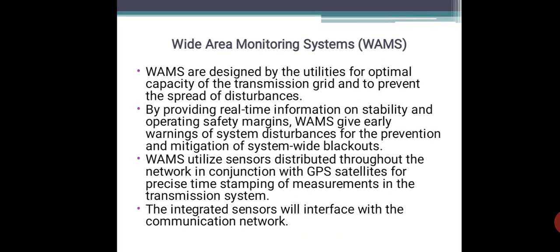Now let us discuss one of the most important devices in the transmission system, that is the PMU. The long form of PMU is phasor measurement unit. It is also called a synchrophasor. What this device does is take a snapshot of the power system. Let me brief once again. Whatever the bus voltage is, the phasor of that bus voltage and the phasor of the branch current, plus some additional information like the location and other network parameters, are all monitored by the PMU. Along with the bus voltage and bus current, it will take the phase angle also. That's why it is a phasor measurement unit. Along with the magnitude, it will take the phase angle also.